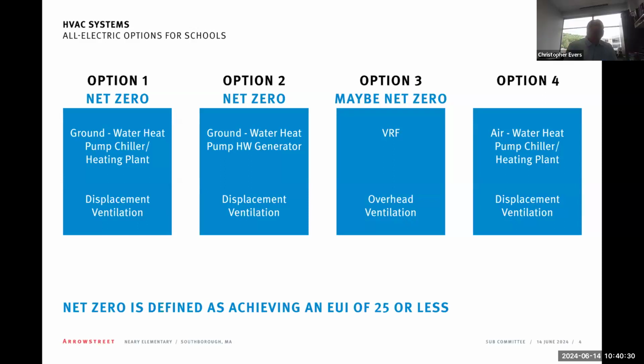Yeah, you're absolutely right. You could do option two with the ground source. The difference is you're using a heat recovery chiller, right? The main difference is option 2 doesn't have a chilled water line. So it'll be conditioned air, it'll be dehumidified, but the set point is going to be 78. Couldn't you add an air source heat pump on the ground or on the roof to option two? Air source chiller, excuse me.